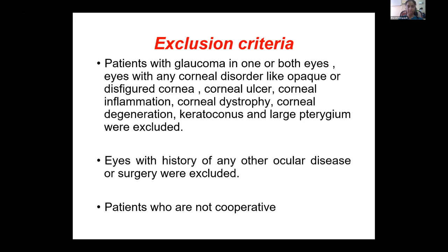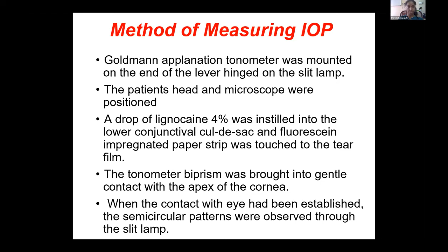Method of measuring IOP. The Goldmann applanation tonometer was mounted on the end of the lever hinged on the slit lamp. The patient's head and microscope were positioned. A drop of lignocaine 4% was instilled into the lower conjunctival cul-de-sac and a fluorescein impregnated paper strip was touched to the tear film. The tonometer biprism was brought into gentle contact with the apex of the cornea. When contact with the eye had been established, the semicircular patterns were observed through the slit lamp. The slit lamp was then raised or lowered until the two semicircles were equal in size, and the tension dial was adjusted so that the inner edges of the upper and lower semicircles were aligned.